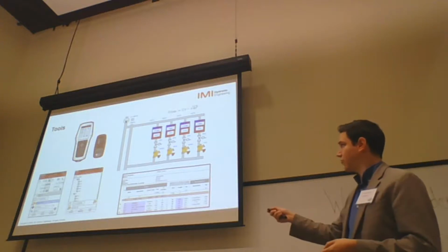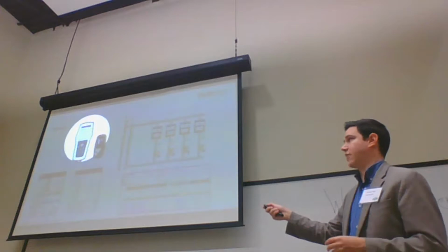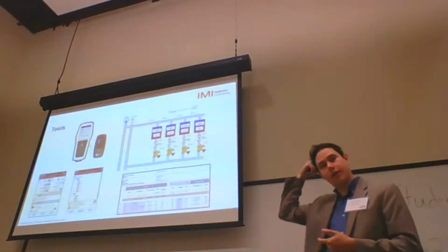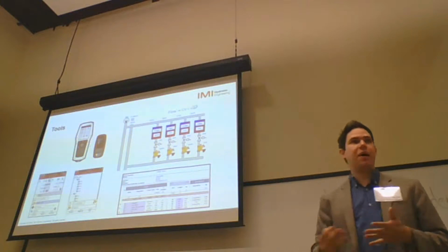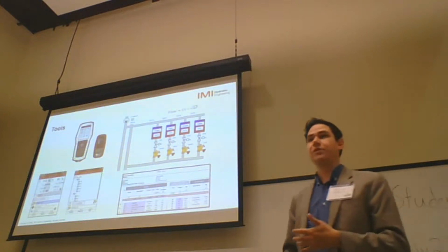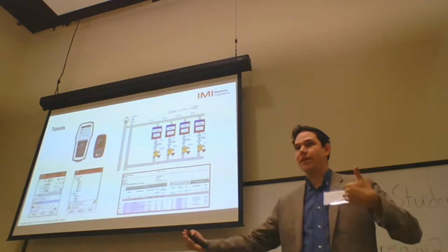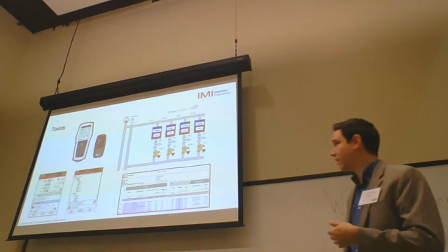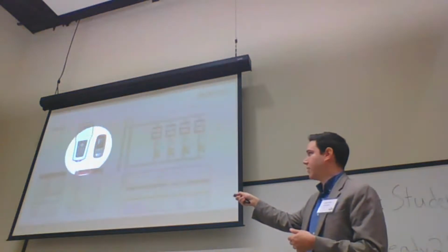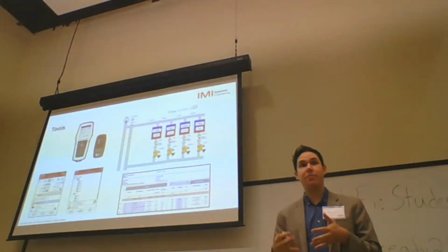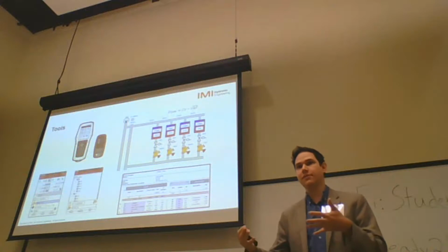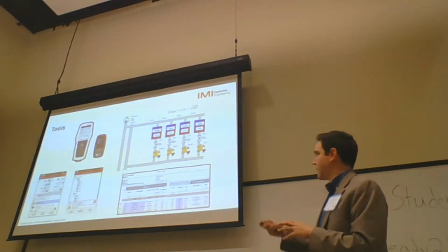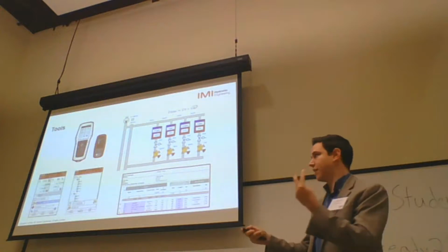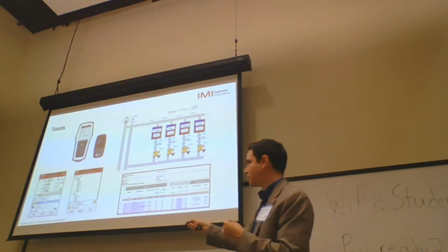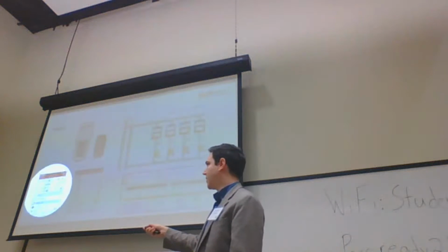Another thing that is possible to do is with the balancing device. So a balancing device like this one, you do have balancing methods that can save time on the installation and how quickly you can finish hydronic balancing. This equipment has inside a balancing method that is called TA wireless. And the wireless method is basically using 2 DP sensors at the same time. And when you use 2 DP sensors at the same time, the screen is divided by 2. So you see 2 measurements at the same time.